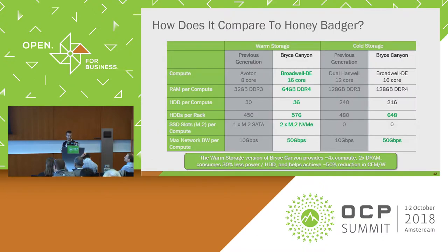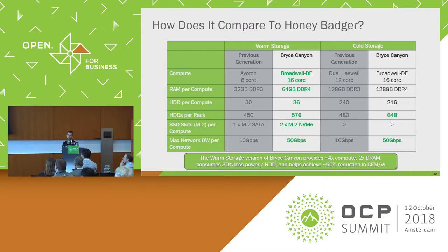How does it compare to our previous Honey Badger chassis? We improved a lot of aspects — not only system performance but also about four times the amount of compute per drive, increased DRAM, less power consumption per drive slot, and about a 50% reduction in CFM per watt for the entire chassis, which is huge for a forced air cooling data center like Facebook.